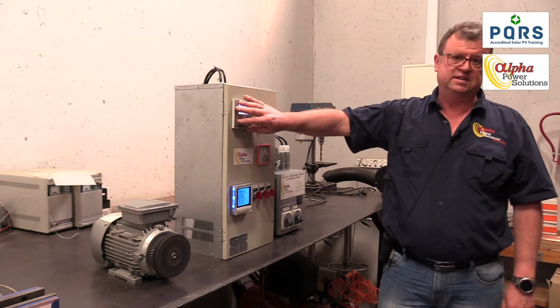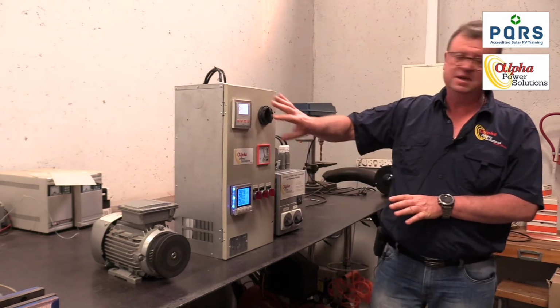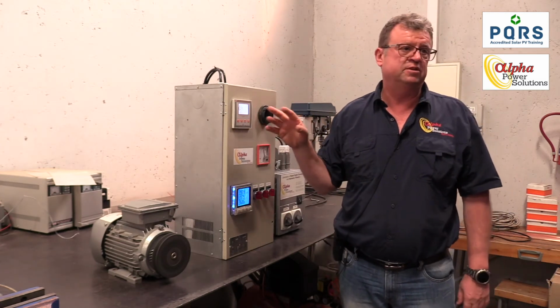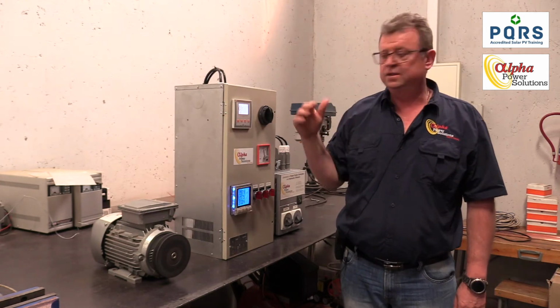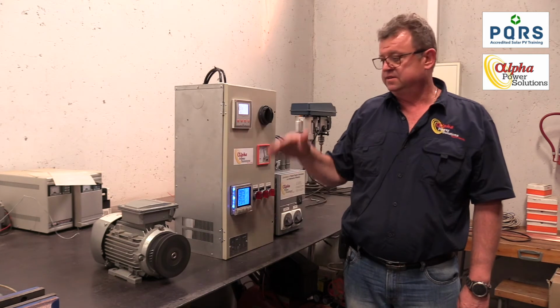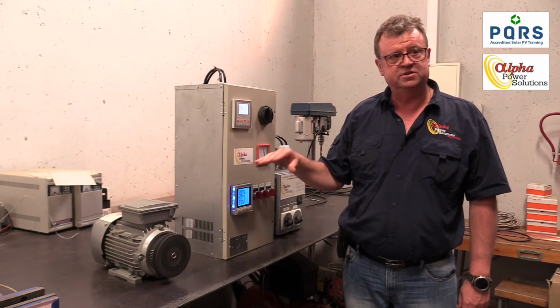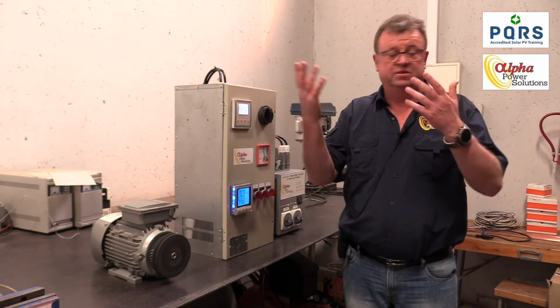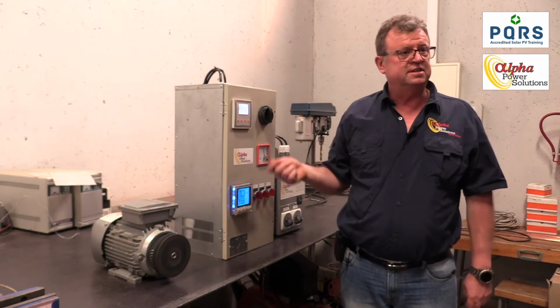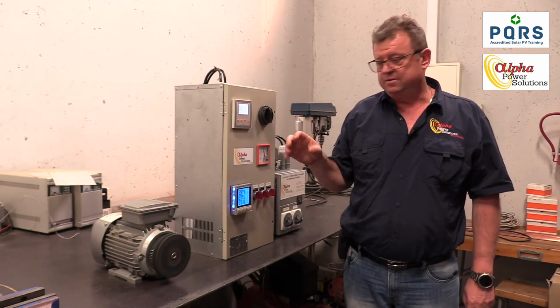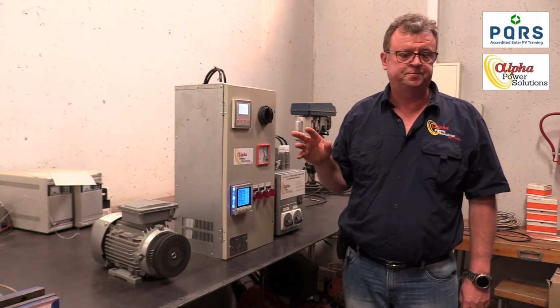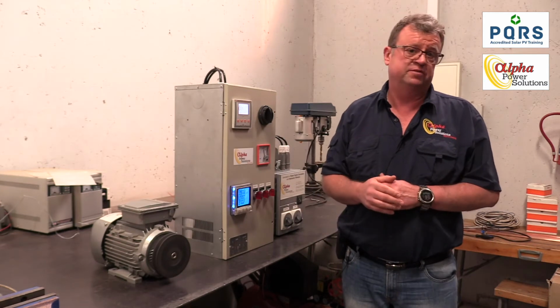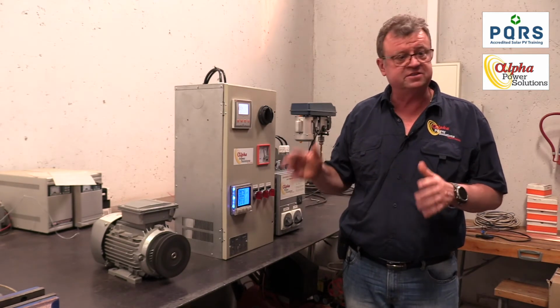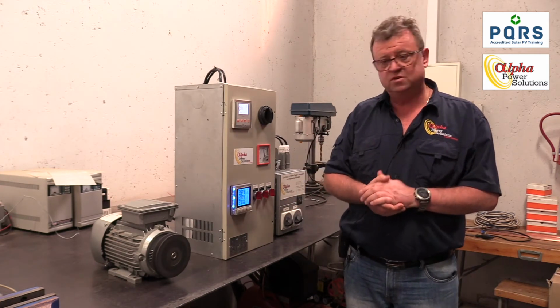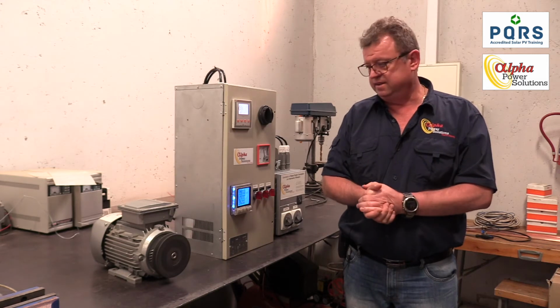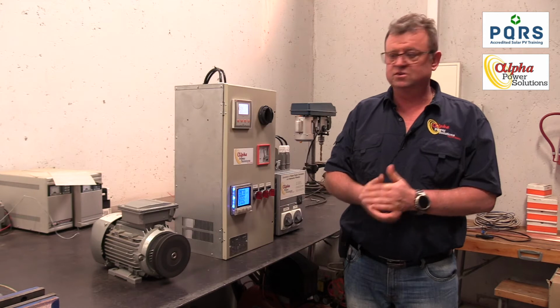So also this device here, it's actually quite a clever device. You can program many things. You can prevent this unit from operating when the voltage exceeds a value that you have set. The purpose of that is that you don't blow up the capacitors inside. Similarly, you can also set the minimum voltage, so that if the voltage drops for whatever reason, there is a risk that the contactors will start rattling. And with capacitors, it's extremely destructive. Switching capacitors is extremely aggressive. It's one of the most aggressive things you can switch on or off. The capacitors will fight any change. And so if a contactor starts rattling, it actually destroys them extremely fast. So we set the minimum voltage.